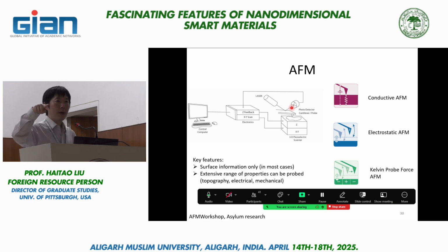You can also do it in a different way. You can decide, I'm not going to do any vibration. I'm just going to use it as a needle. I'm just going to touch the surface and get a feeling of what kind of stuff is on the surface. That's an oversimplified way. But if you do it that way, you can also get an image that's called contact mode. You have more interaction with the substrate, but you get more forceful intrusion of the surface. If you have a liquid layer or something viscous, that may be masking the contact mode imaging.